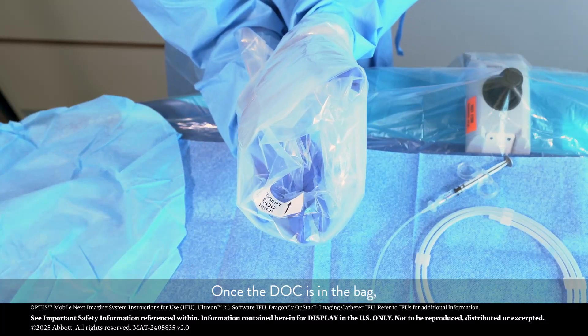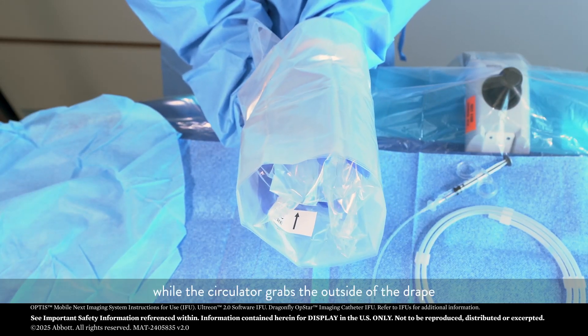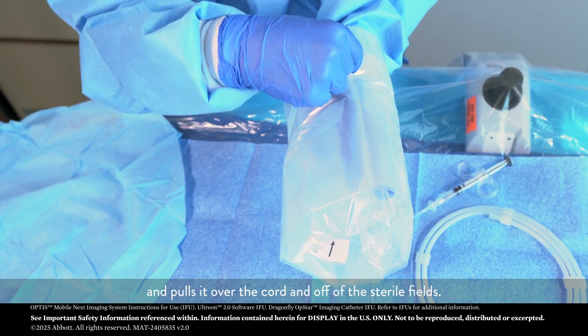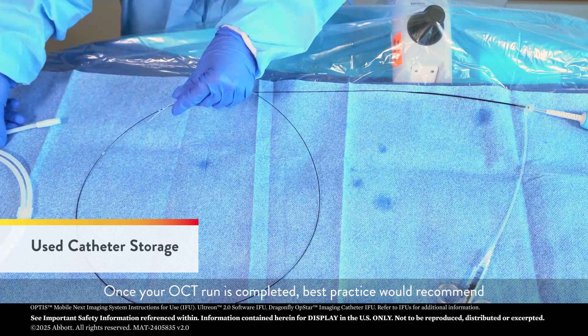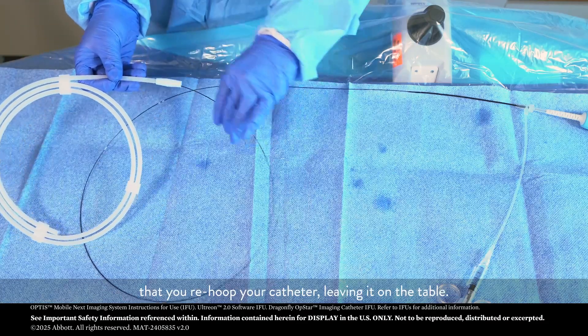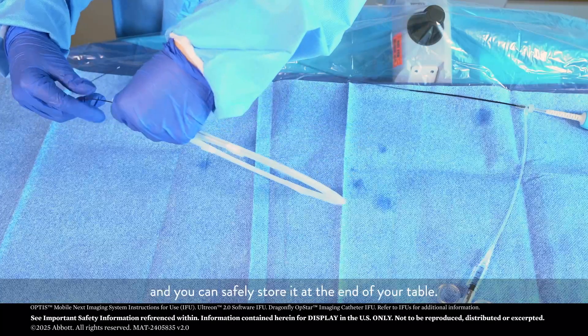Once the DOC is in the bag, you want to make sure that you firmly grip and hold the DOC, while the circulator grabs the outside of the drape and pulls it over the cord and off of the sterile field. Once your OCT run is completed, best practice would recommend that you re-hoop your catheter, leaving it on the table. You can leave your catheter connected to the DOC during this time and safely store it at the end of your table.